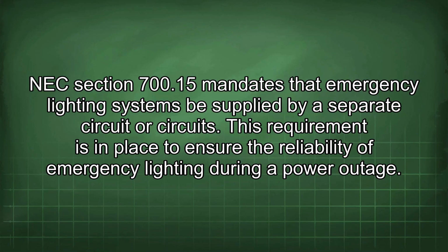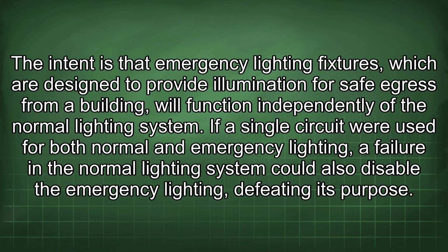NEC Section 700.15 mandates that emergency lighting systems be supplied by a separate circuit or circuits. This requirement is in place to ensure the reliability of emergency lighting during a power outage. The intent is that emergency lighting fixtures, which are designed to provide illumination for safe egress from a building, will function independently of the normal lighting system.